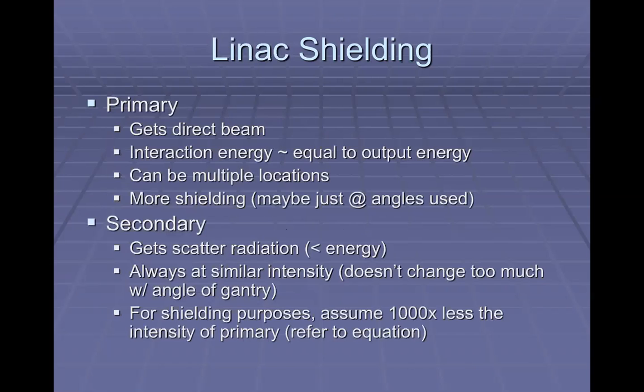And then we get to Linacs. Linacs are where we know there's going to be very, very intense, very, very directional, very, very high energy photon sources, radiation sources. So we need to account for that in a number of different ways. And so when you're looking at designing a Linac vault, you really take into account two separate factors. A Linac gantry will rotate in a single plane. It rotates in a full 360 degrees, but in a single plane.